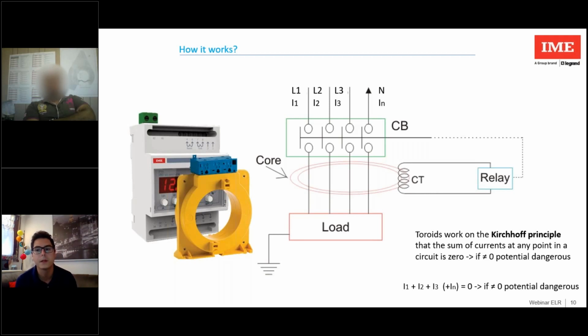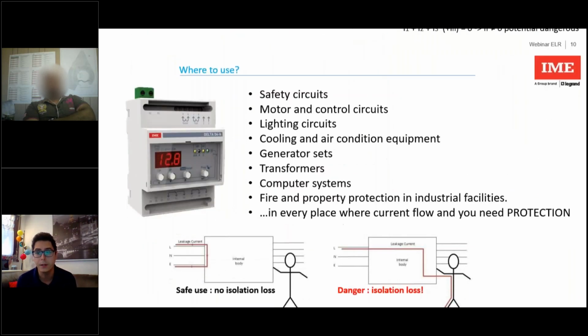This current value is reported to the relay, which compares it with the set threshold. And as I said, if the current exceeds this threshold, the relay trips and opens the supply circuit, removing the voltage from the circuit. So, where can I install this differential relay?